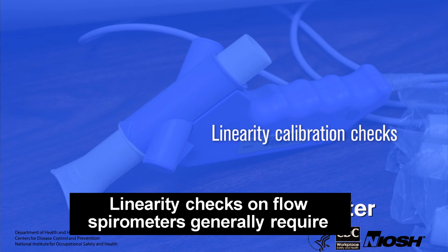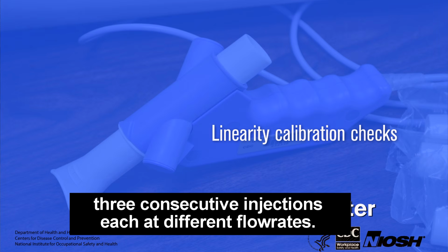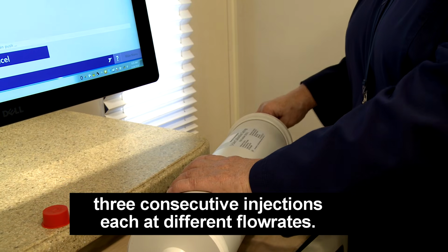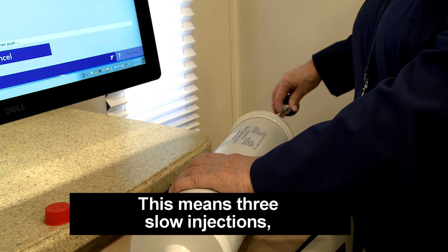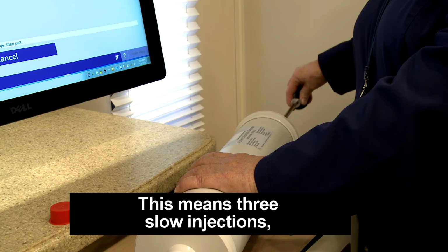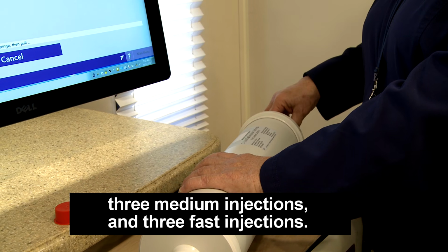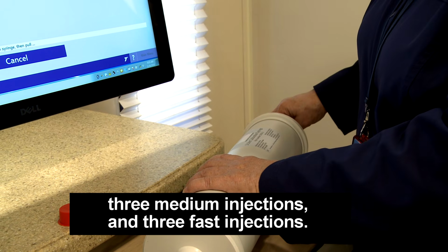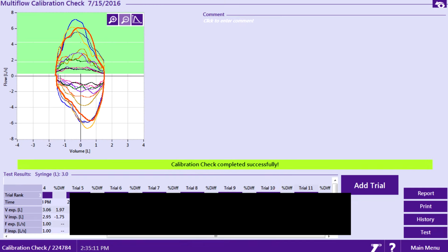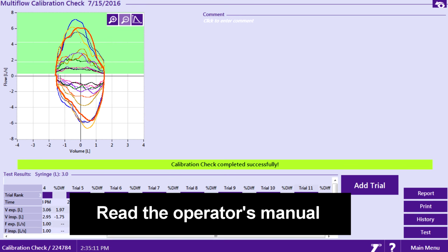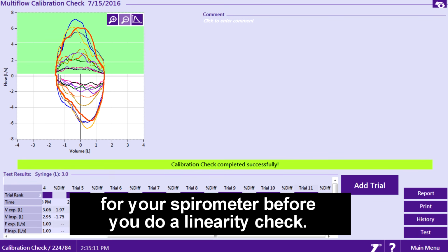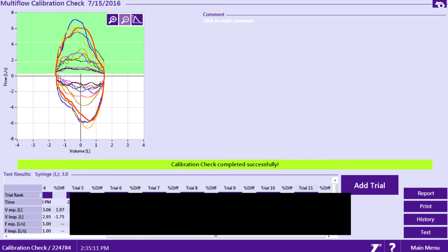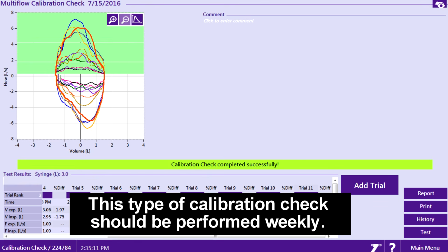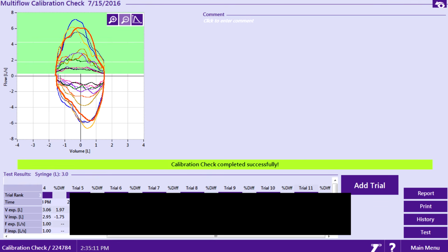Linearity checks on flow spirometers generally require 3 consecutive injections, each at different flow rates. This means 3 slow injections, 3 medium injections, and 3 fast injections. Read the operator's manual for your spirometer before you do a linearity check. This type of calibration check should be performed weekly.